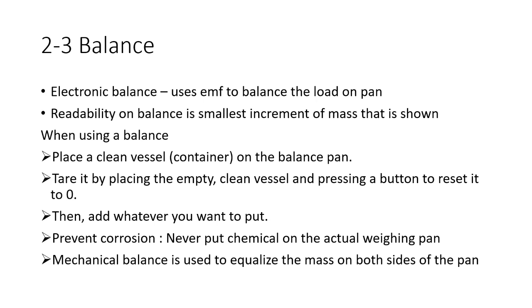You need to tare it by placing the empty clean vessel and pressing a button to reset it to zero. Then add whatever you want to put. To prevent corrosion, never put chemical on the actual weighing pan. Mechanical balance is used to equalize the mass on both sides of the pan. That's like your typical middle school and high school balance pans. If it's not equal, you need to put more mass or take out some mass.